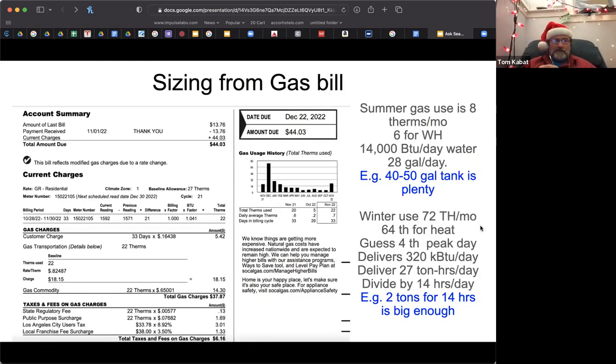I did some sizing of equipment for them by looking at their gas bill. Up here in PG&E territory we get nice daily gas data, which makes it easy to see how much energy is used for different things. But here I had to make a couple of quick guesses. The summer gas use, shown at the low part of this graph in the middle, was about 8 therms per month. Probably 6 of those therms went to the water heater, the other 2 for cooking and drying. With 6 therms per month going to the water heater, that's only about 14,000 BTUs per day, making it about 28 gallons a day of hot water. So a 40 or 50 gallon heater tank will be plenty.